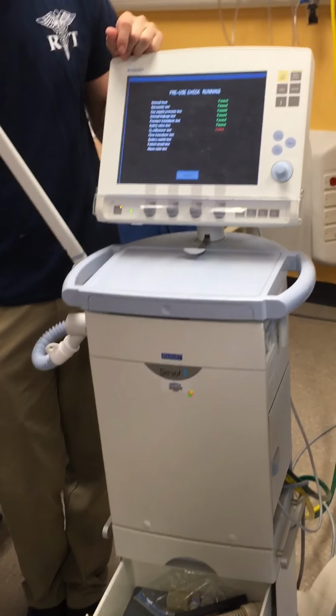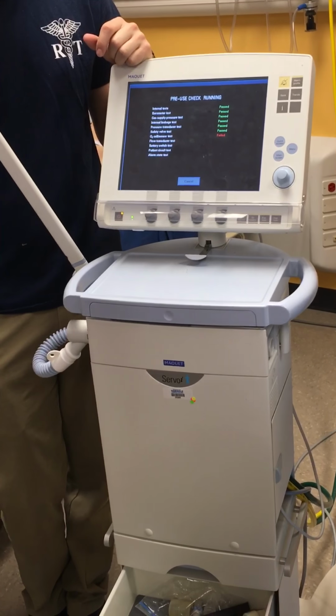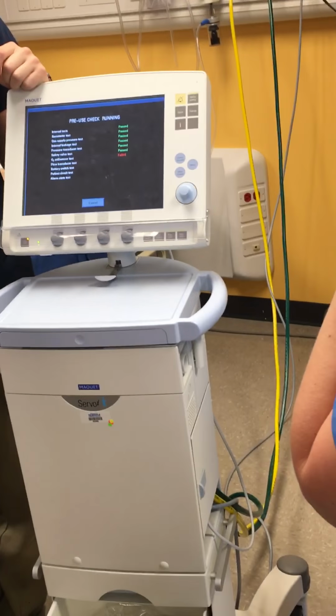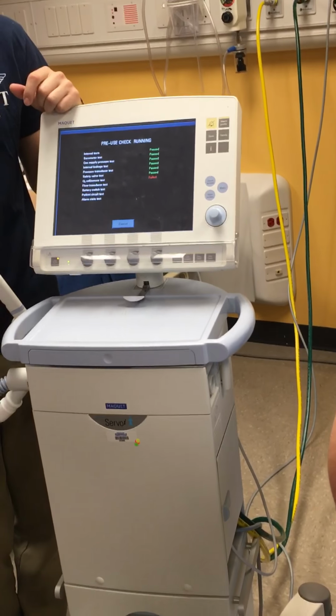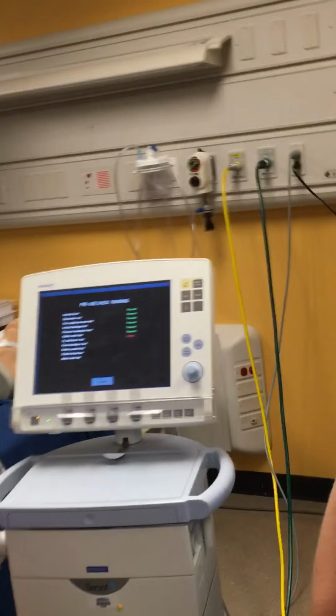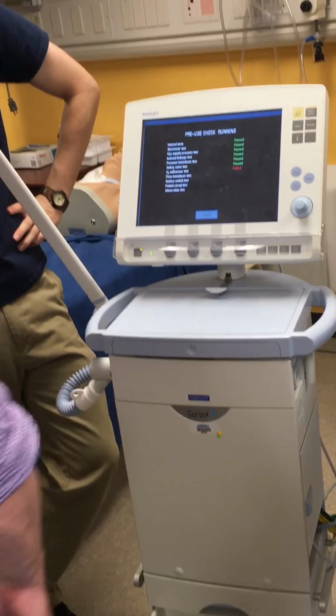Now it's calibrating its flow transducers. Is it going to fail on all of them? No, it's going to fail the battery too. So when we see that, we don't have to panic, because these are where the batteries are. You can load batteries up here. And the more battery packs you put in there, the longer it runs without electricity.